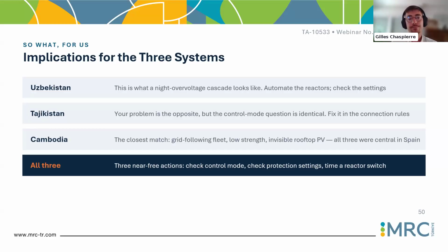response to voltage deviation. For Cambodia, it's actually the closest match because most of the time you have a low-strength system, invisible rooftop PV, and a majority of grid-following fleet. Which are, I would say, three ingredients that were quite central in the blackout in Spain and Portugal. But as I will explain later, there are immediate actions that you can take, easy checks to make sure that the control mode, or how the connection and disconnection of shunt reactors is handled in your system, is going in the right direction. And if not, do a kind of gap analysis and take appropriate action to update it as fast as possible to avoid this kind of very fast voltage rise that can eventually lead to system issues.